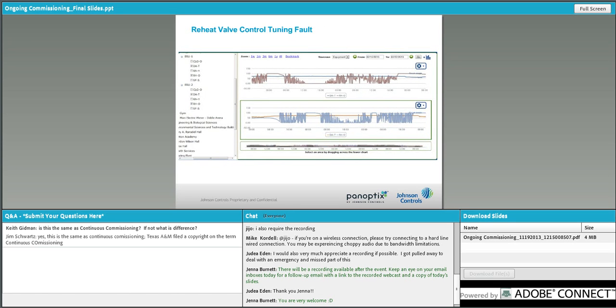This is a fault that shows a reheat valve that is just out of tune. The up and down line here is the output to the control valve command, from 0 to 10, 0 being closed and 10 being wide open. You can see it just keeps hunting up and down, opening and closing. There could be multiple causes for this. The control loop may need to be retuned, or the control valve could be oversized. But there is a problem there, and it causes excessive wear and tear on the valve and the actuator of that control valve.